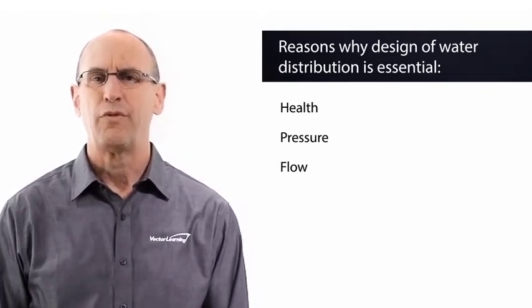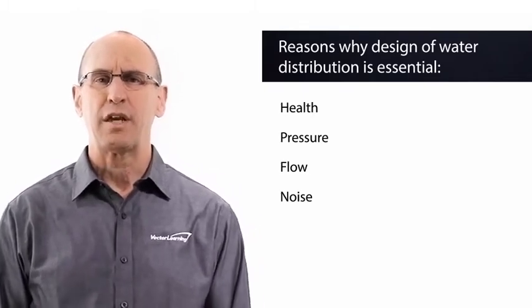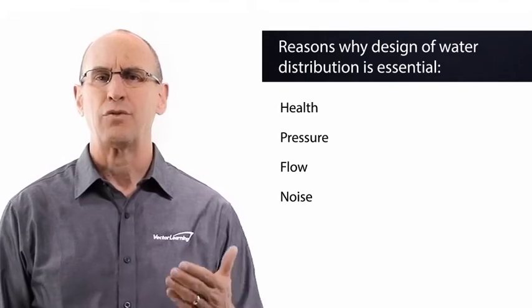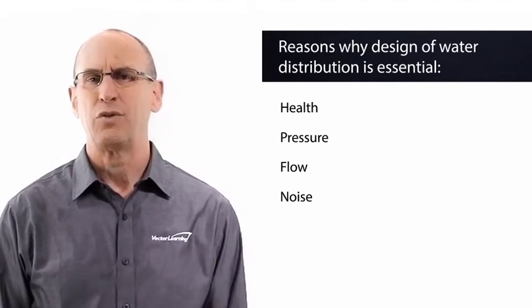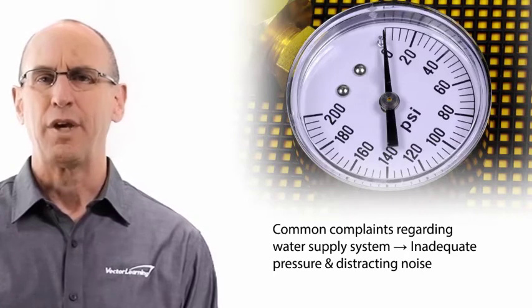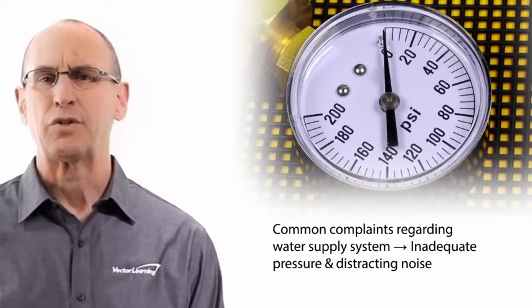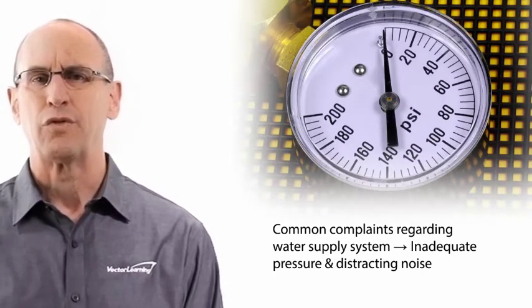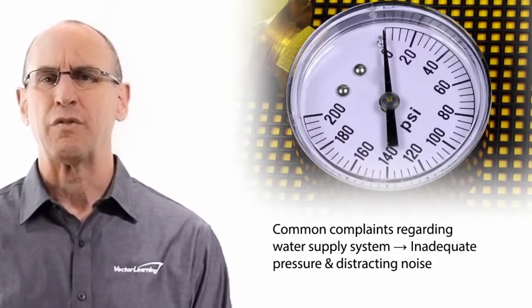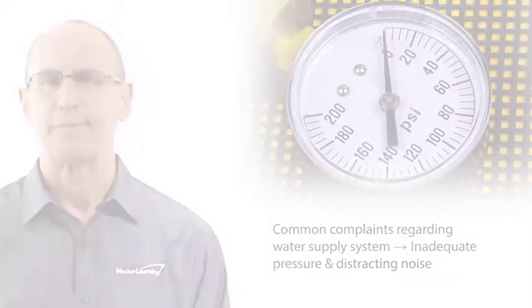Number four is noise. Velocities exceeding ten feet per second will result in excessive noise and can also cause hydraulic shock to the piping system. Some of the most common complaints regarding the water supply system are inadequate pressure and distracting noise from water flow. Noise is not detrimental to the operation of the system, but it can be a major nuisance for building occupants.